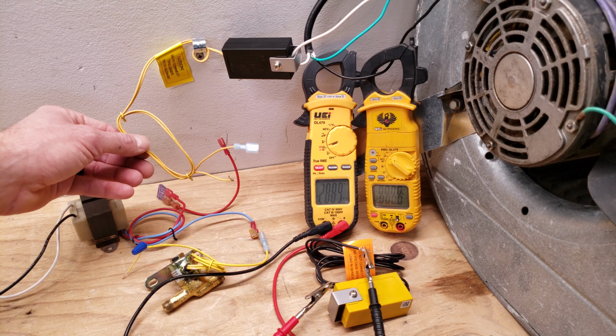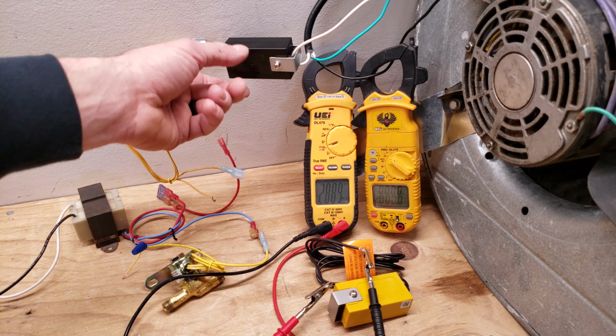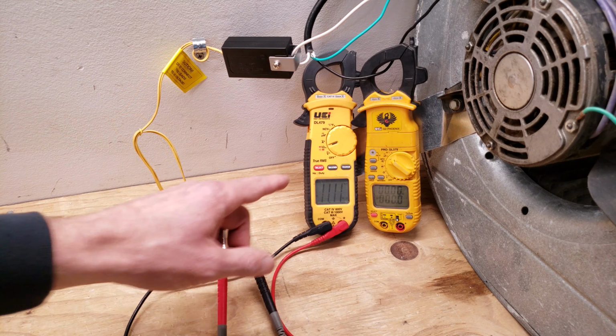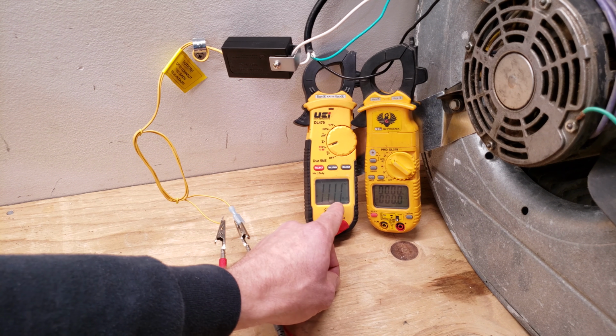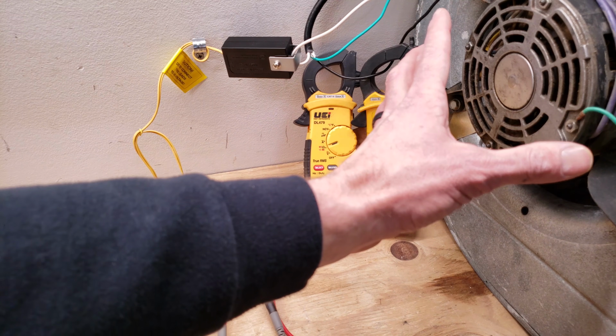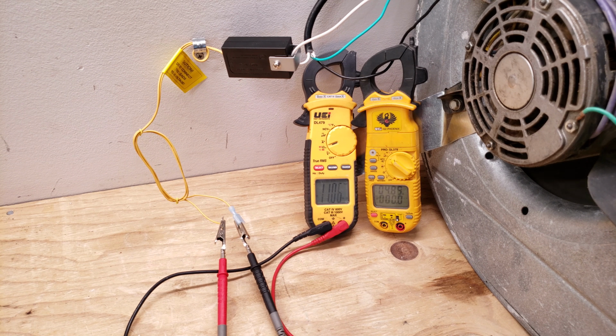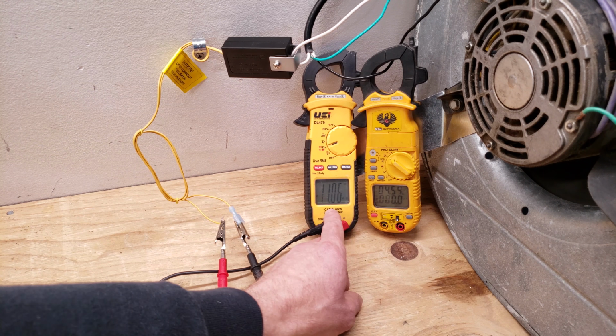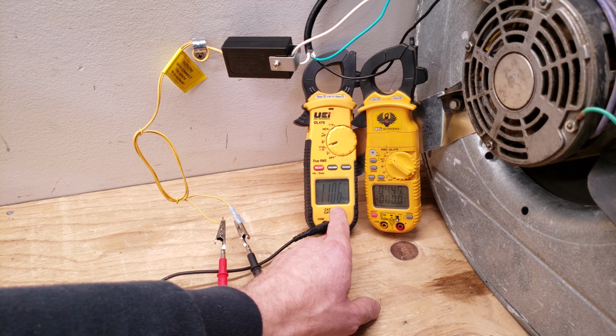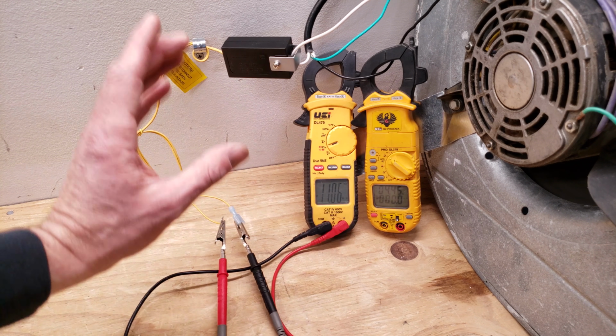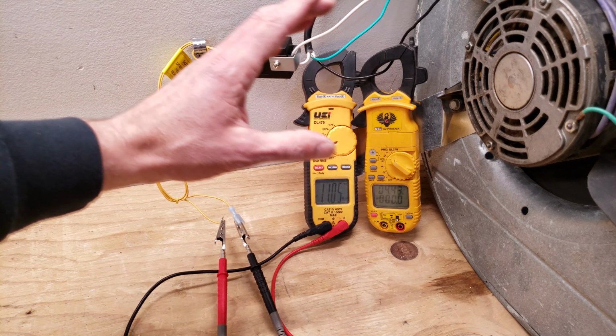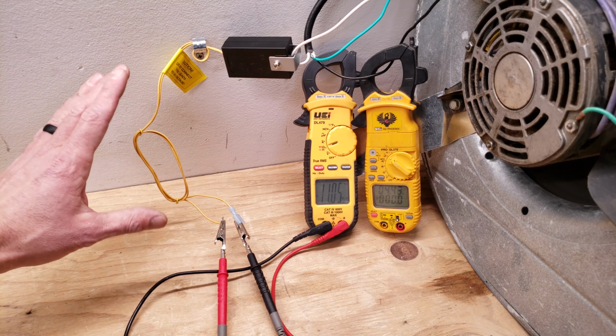So I'm going to show you the resistance value on this while the blower motor is running. Presently we're reading 11.1 mega ohms. Now we're going to turn the blower motor on. And you see that we're still reading 11.0 mega ohms. So you can't troubleshoot it while the blower motor is running and drawing amperage. You have to have the 24 volts.